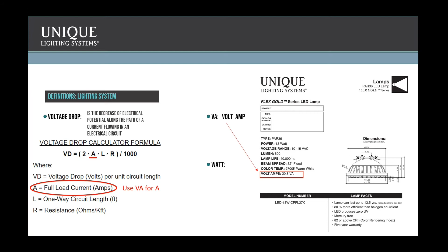The way to think about watts is that watts is how we perceive how bright or how dull a lamp is. Here's this cut sheet from Unique describing this PAR 36 LED lamp. You can see it has a power rating of 13 watts, but it has a volt amp of 20.8 VA. This is the number we need to understand and use when doing our voltage drop calculations.